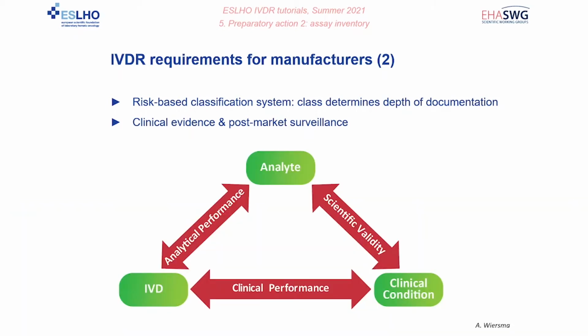Let's have a quick look at this figure, which depicts well how these types of evidence relate to each other. Scientific validity concerns the relation between clinical condition and the analyte. Analytical performance connects the device with the analyte, and clinical performance connects the device and the clinical condition.